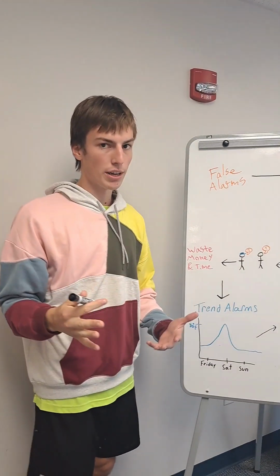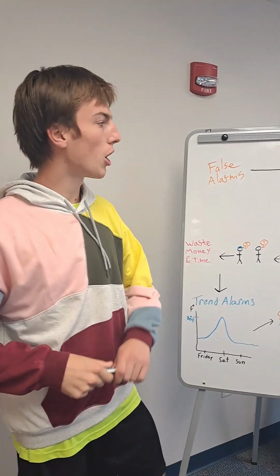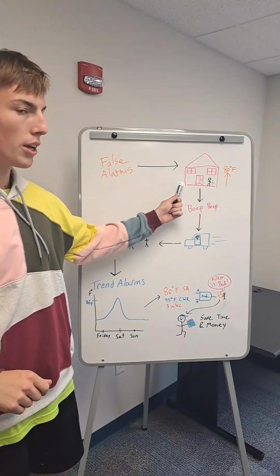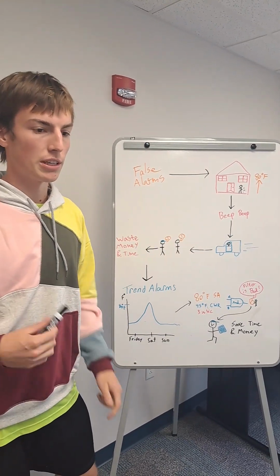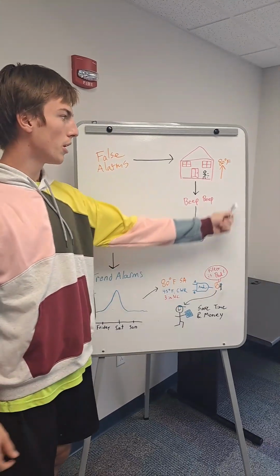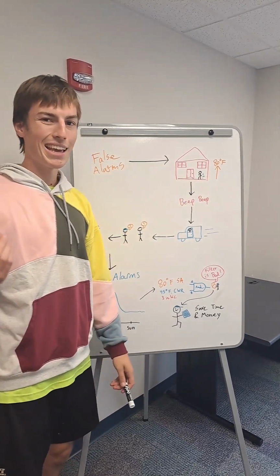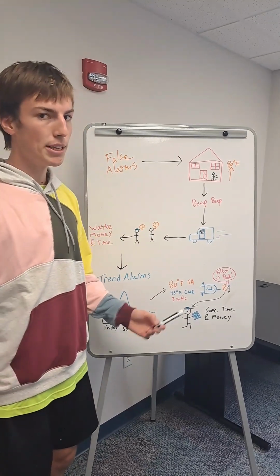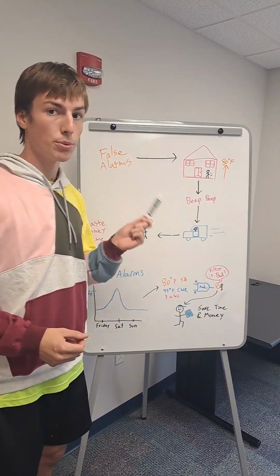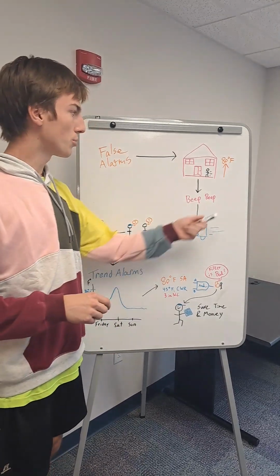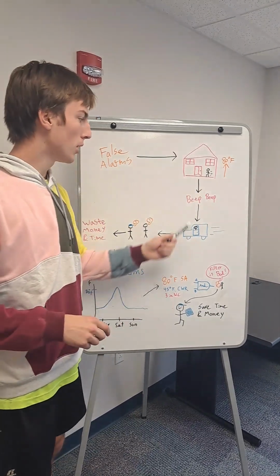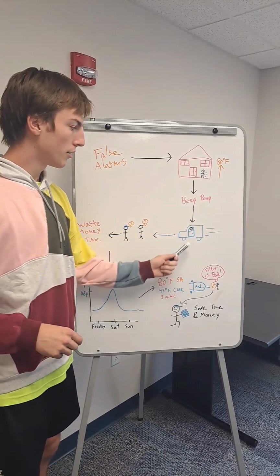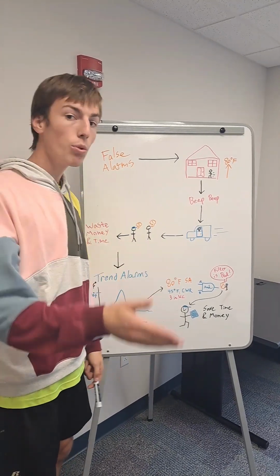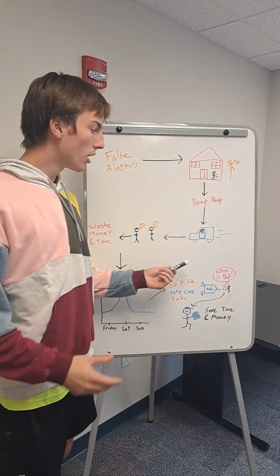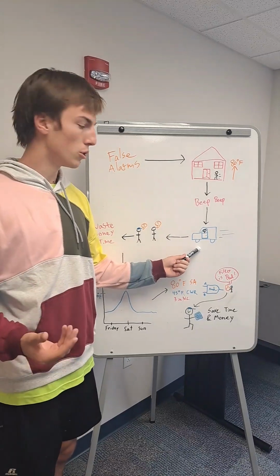I mean, we have the right alarms installed, we have the temperature alarms, but on Saturday, some people decided to move stuff into their office. They prop the door open, the temperature spikes up to 80 degrees, and immediately the important alarm that we set with our customer goes off. Beep, beep, beep, beep, beep. Look at that. And the poor technician has to drive all the way out to that office building because of the false alarm, because no one notified him.